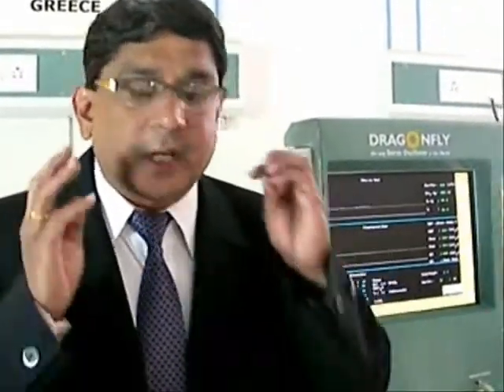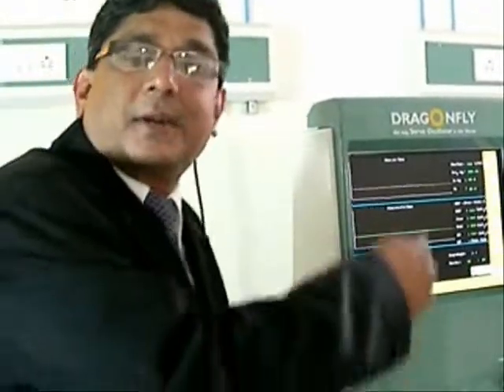But what happens? As a clinician, we have designed this equipment considering that the clinician should concentrate only on the patient and not on the machine. So each time a clinician adjusts the flow, he has to again go and adjust the pressure. Or in case the clinician adjusts the amplitude, again the pressure changes in the Sensormedics 3100A. Why? It's simple. If you increase the amplitude, the distance traveled by the piston increases. So obviously more gas goes into the lung. So that increases the pressure, as simple as that.